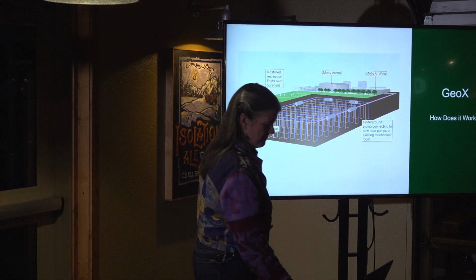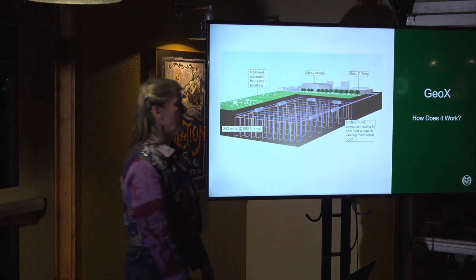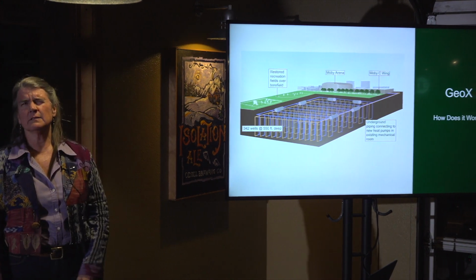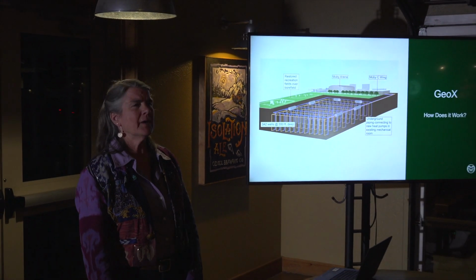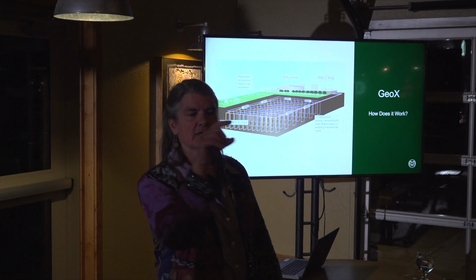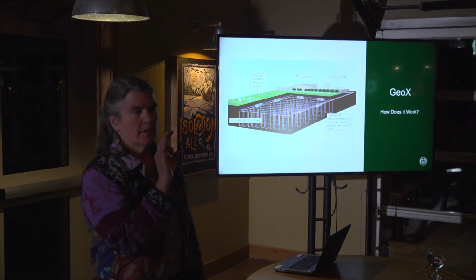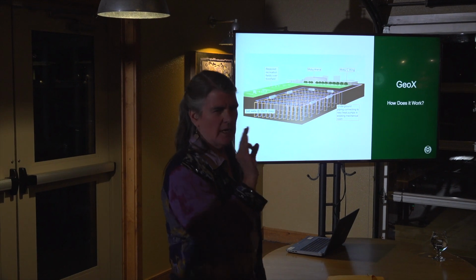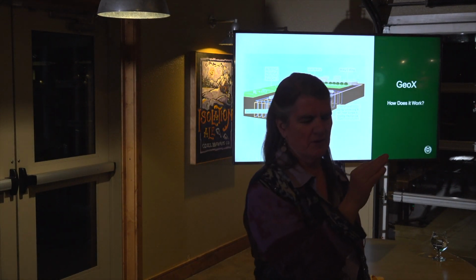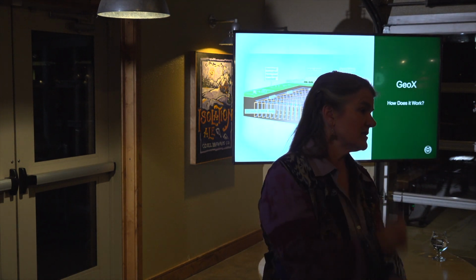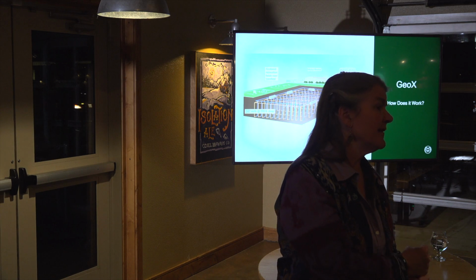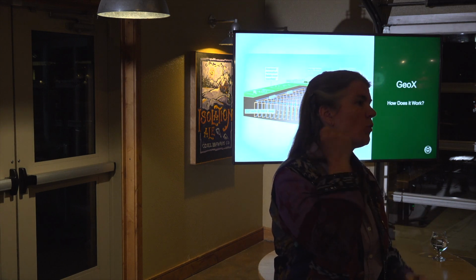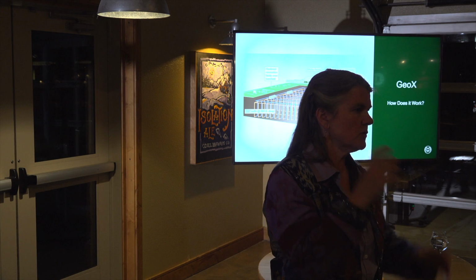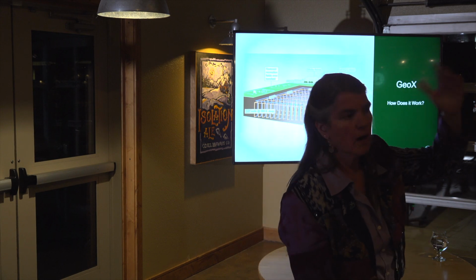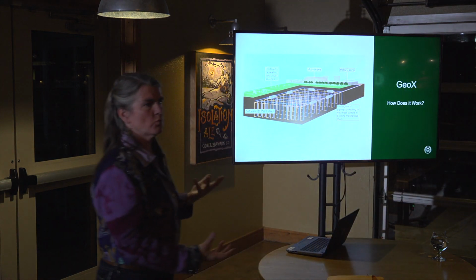Someone asked where the water table is—great question, we actually hit water at 12 feet. But that doesn't really matter here because each borehole has a U-shaped pipe, about 1 to 1.5 inches in diameter, running 550 feet down and back up. After drilling, they immediately fill the well with conductive grout, sealing it right away so there's no contamination between aquifers. It's a fully closed well once they're done.